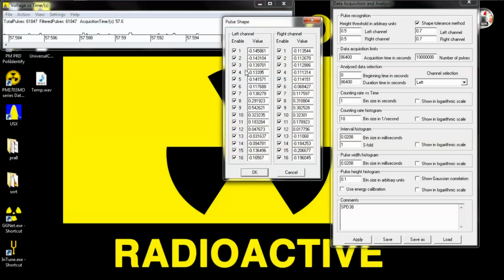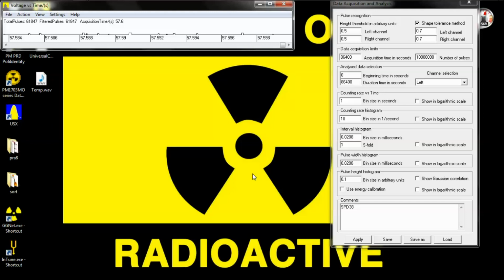This box will pop up, pulse shape. These values indicate the pulse shape, and you might be immediately thrown, saying, whoa, look at all these crazy values. How am I supposed to know that? Well, you don't. This is showing you what the machine has set it to. For the starting beginner user, you can click OK and just let the unit go with what it decides. It'll probably be OK. Now, let me show you what a cesium-137 spectrum should look like.